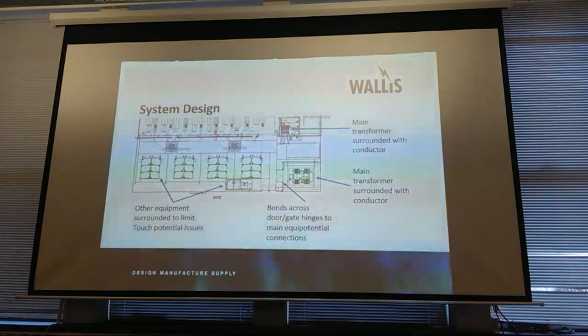This is just a little representation of what we did on the site. It's a 33 kV connection, coming in from the bulk supply point, only a couple of 100 meters away. It transforms down from 33 to 11, and the actual generator sets would sit up here somewhere. We're actually outputting at 11 kV. There was a little HV to LV transformer just for auxiliary supplies in there.